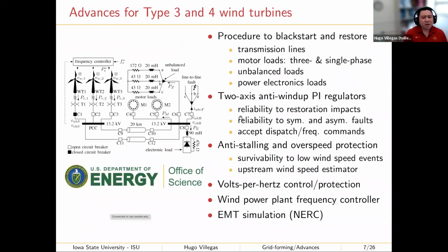In order to achieve that, we have to make several contributions to grid-forming technology. First, we introduce a procedure to black start and restore systems. In black start and restoration, the goal is to re-energize, for example, transmission lines, and to energize motor loads, which can be of two types: three-phase motor loads, or single-phase motor loads, for example in air conditioners. Three-phase motor loads could be, for example, in the auxiliary systems of industry. It could be for pumping water.